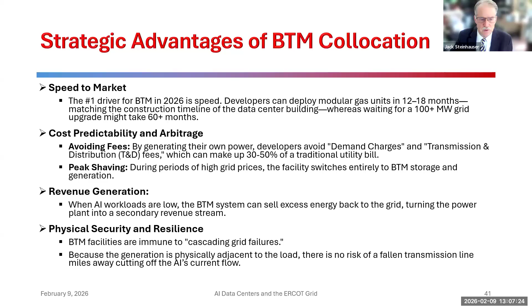But there are some challenges to going off grid—it's not a silver bullet. If you put in a natural gas powered facility, you've got to bring that natural gas in, and there are logistics issues there too. There's also regulatory friction, since utilities may not like the idea that you're jumping off their load but still want access to their power grid when you want it, so they may charge some kind of fee for that arrangement. And if you have a hydrocarbon powered generation facility, you also have to obtain air quality permits—getting that permit is one of the key thresholds to go through.